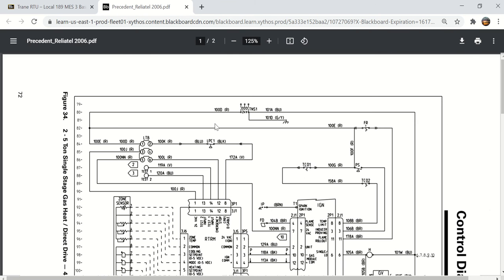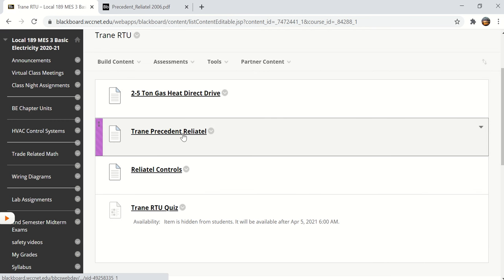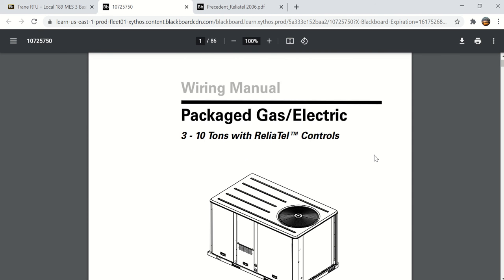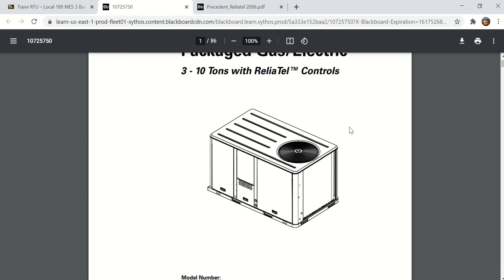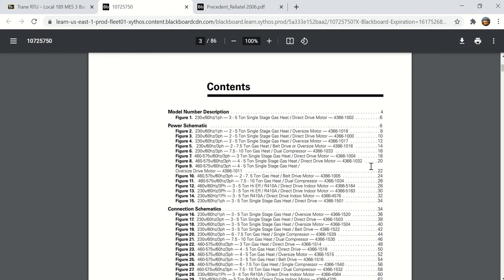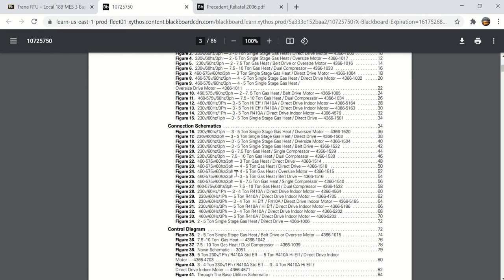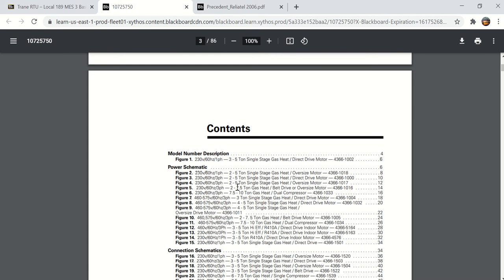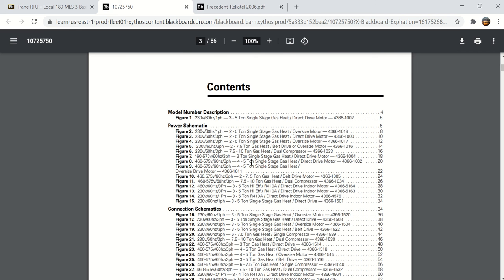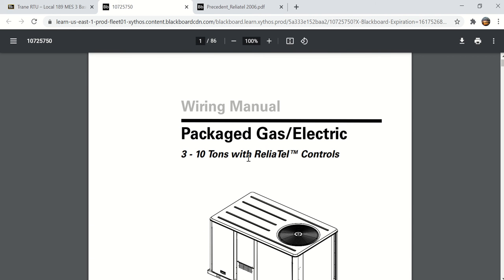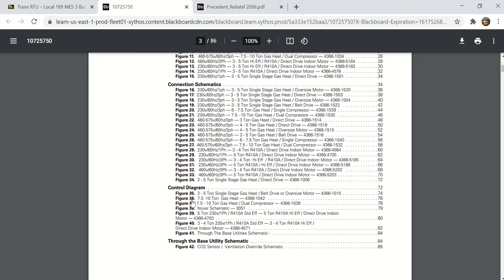So before I go any further with the wiring diagram, I want to go back and open up this document here. It's called Trane Precedent Reliatel. A lot of people say that these units are the President units. They're not President, they're Precedent. And this manual here is the wiring manual for the Reliatel. That wasn't actually the one I wanted to open up, but since I did, here you'll see all the wiring diagrams for all of the units from a 2 to 5 ton up to 10 ton. I think that's what this tells you, is 3 to 10 ton Reliatel control units. The control drawing that we're going to be looking at is figure 35, the 2 to 5.